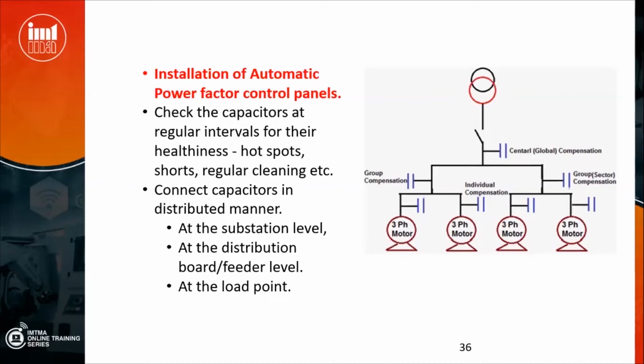See, when I say power factor - generally in inductive loads, and most of our industry loads are inductive: induction motors, solenoid coils, relay coils, induction furnaces, except certain heating furnaces and things like that. If it is induction heating, induction furnace, or arc furnace, they are all inductive. In inductive loads, current lags the voltage - current lags the voltage vectorially. All these are in vectorial terms. So vectorially it lags, and the angle between the voltage and current is called phi. Cos of phi is the power factor.